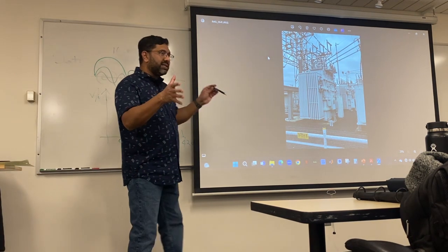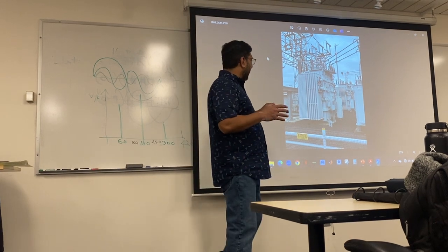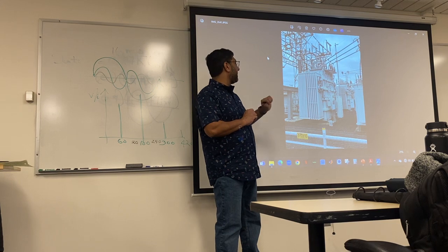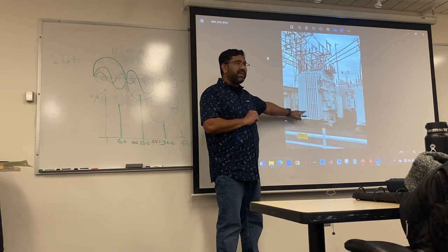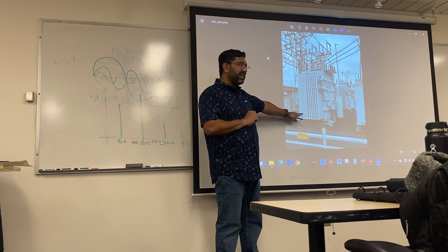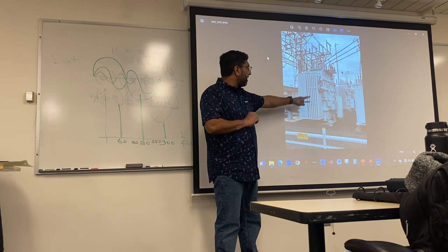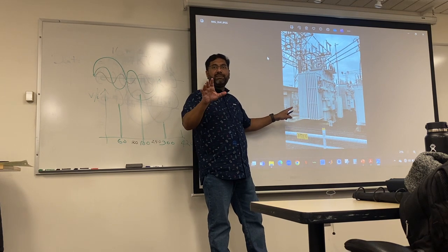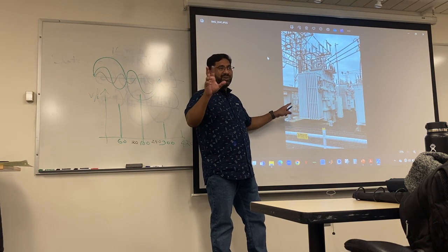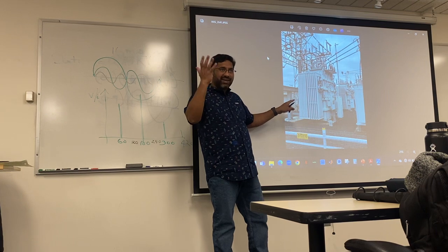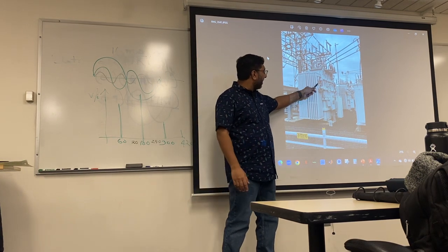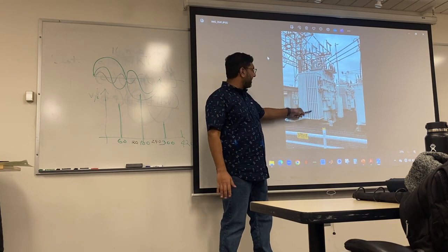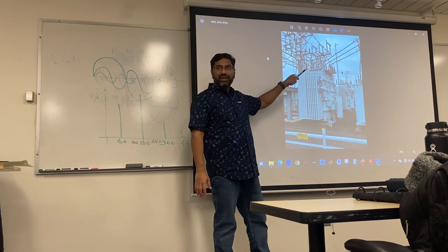Every transformer has a certain capacity. We start with the low end of the capacity, but as we get more Teslas into our system, it's 3 years out. A bunch of people are buying their Teslas. The way we increase the capacity of this transformer is the same way that gamers add a bunch of heat sinks to increase the speed. We keep on adding fans here. That's the easiest way to cool this down and kick up the MVA.